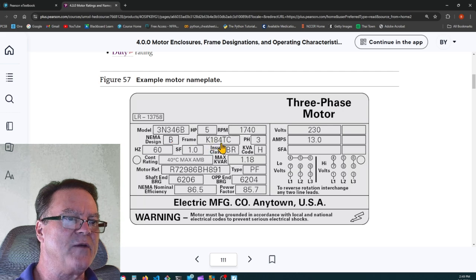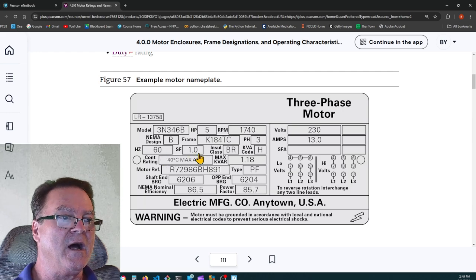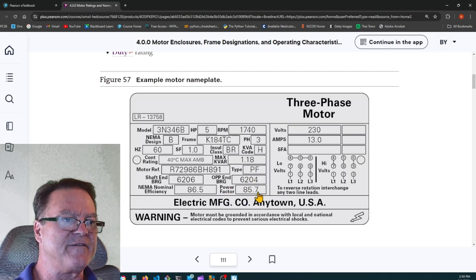So the frame is K184TC. It's 3-phase, 60 hertz. Service factor of 1. We'll talk about service factor later on. And the KVA code is H. Type PF. Power factor is 85.7. NEMA nominal efficiency is 86.5%. It's a 5 horsepower, 1740 RPM.